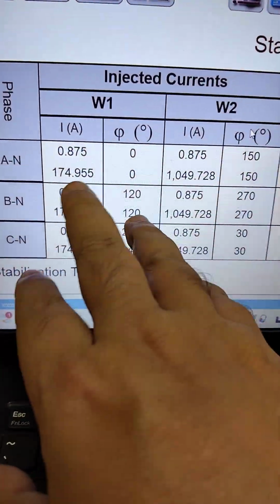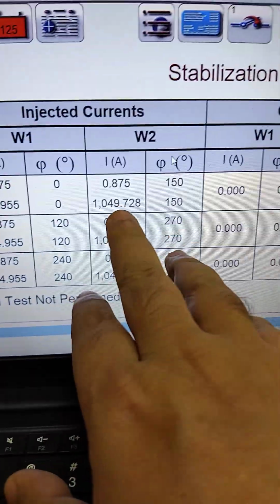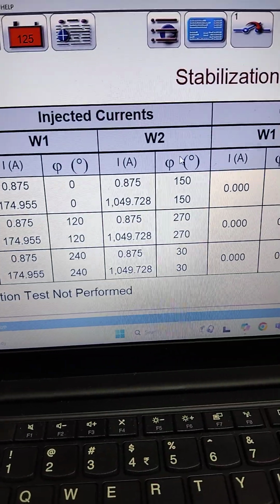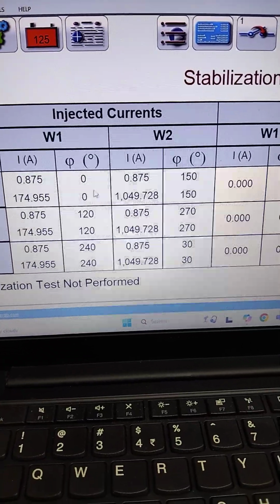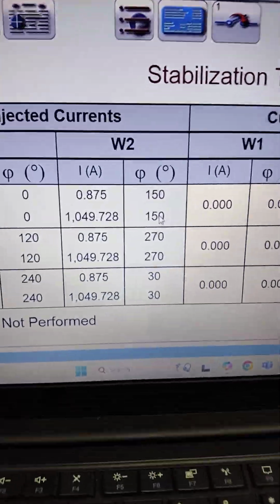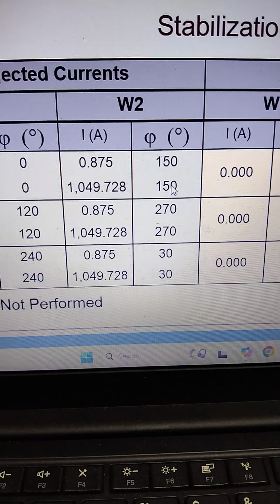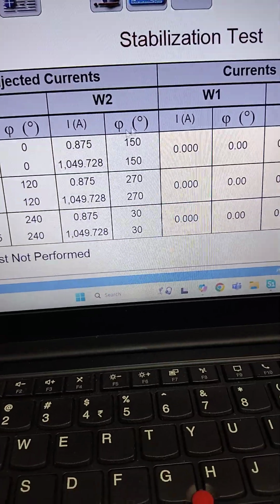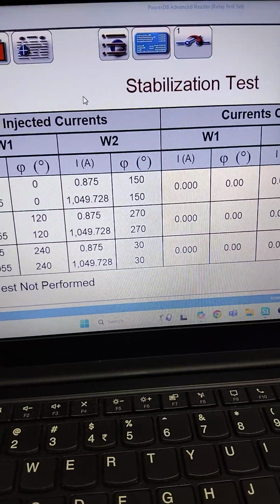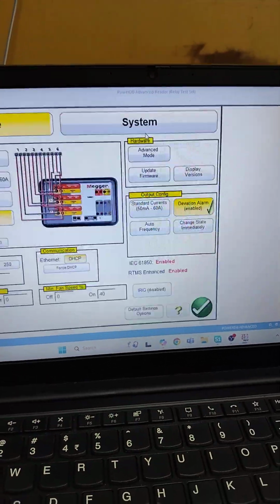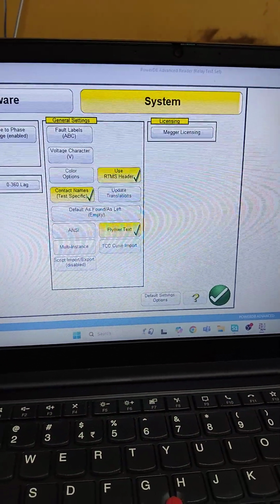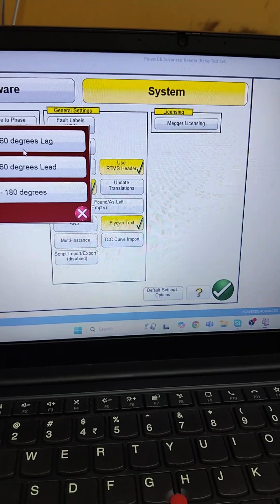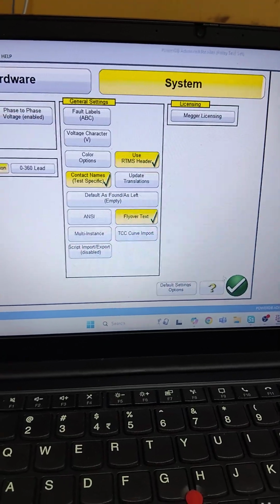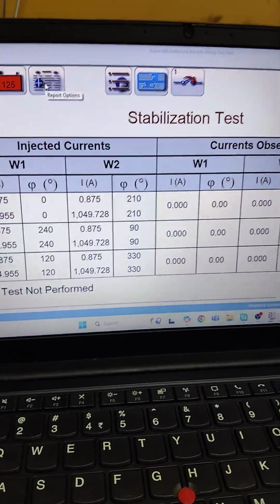So you can check here that 175 and 1050, and since it is a DY11 transformer, there is a vector shift of 180 plus 30 degrees, but as the device here is, I think, not configured correctly, that's why it's showing 150. Otherwise you will see here 210, which is the correct value for DY11.